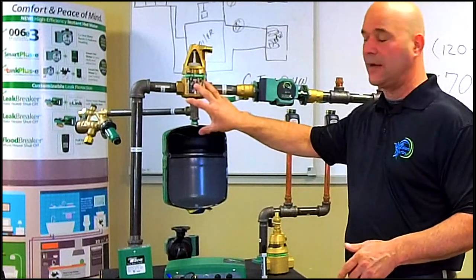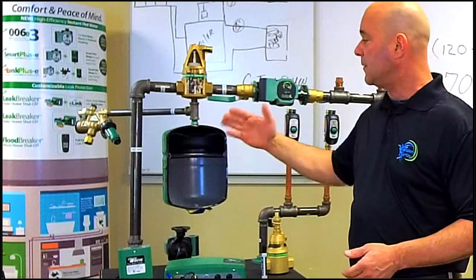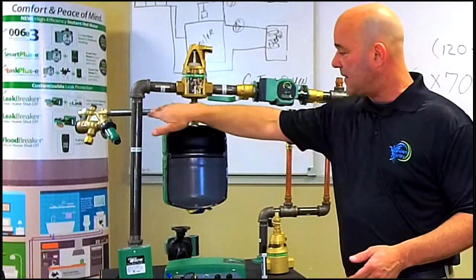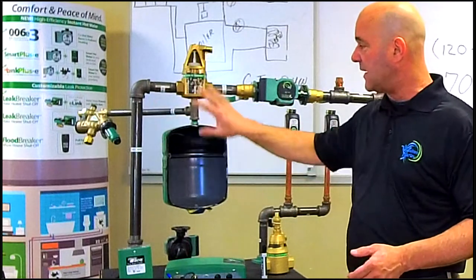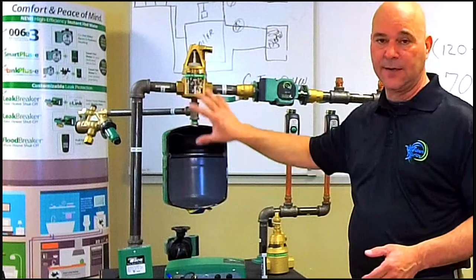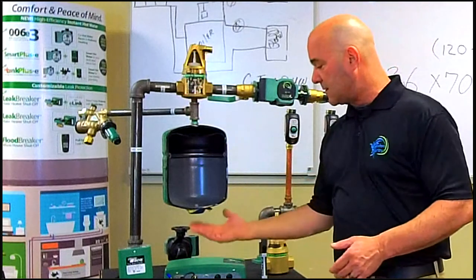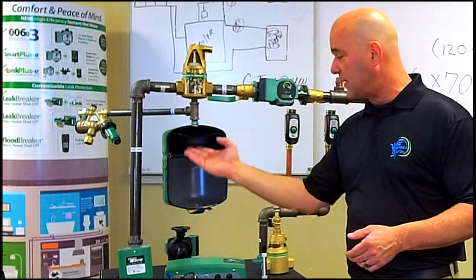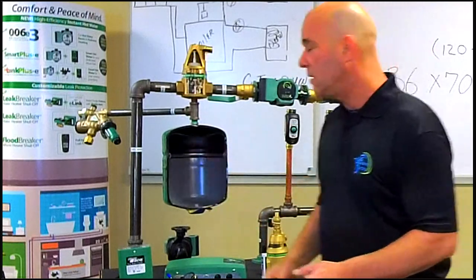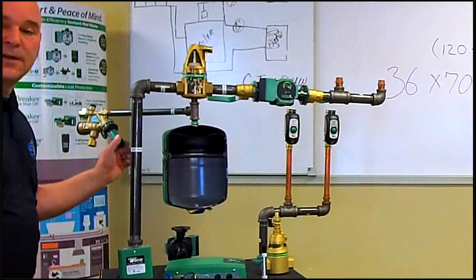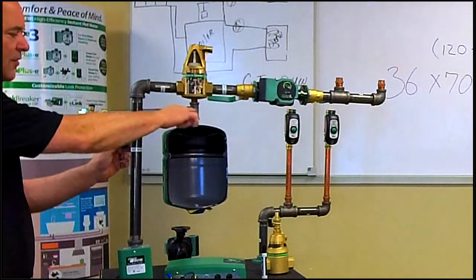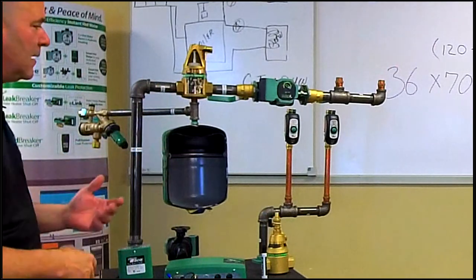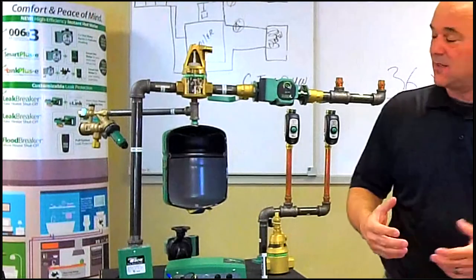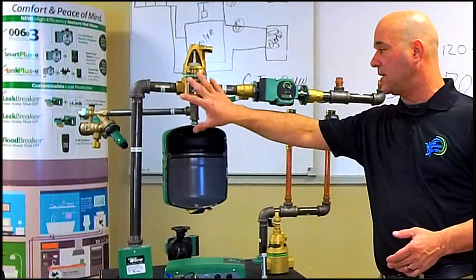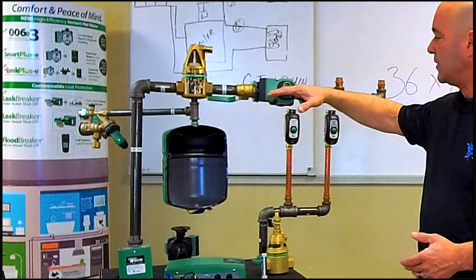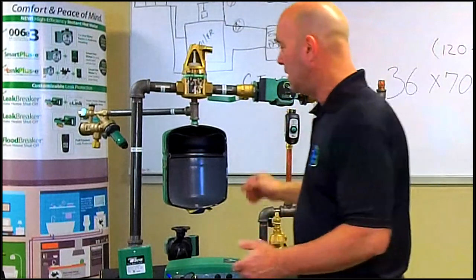This area right here is the area we call the point of no pressure drop. And the reason we call it that is because this is where our feed valve and backflow preventer, expansion tank, and air separator all live right here in this area. So the goal of the expansion tank is to keep 12 PSI. That's what it should come shipped at, 12 PSI on the bottom of this rubber diaphragm. We have this feeder backflow preventer here that is going to maintain 12 PSI of water pressure on the boiler system. And that becomes now a complete system. We got 12 on the bottom, 12 on the top. This becomes the point of no pressure drop. Then we go into our circulator and out to the system.